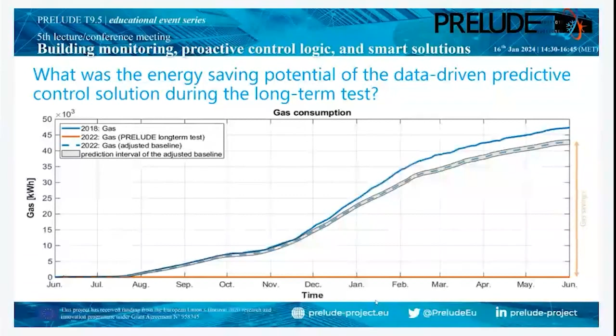Because of the reduction of heat loads in our building, we also switched off the gas boiler at the beginning of our long-term test. In the past, we used the gas boiler for heating purposes. Because of the reduction of the heat losses, we tried to use the heat pump also for heating. Because we only use the heat pump for heating and cooling, we only need electrical energy, we don't need any gas. Therefore, we have 100% gas savings compared to the adjusted baseline. These are more than 4,000 cubic meters, or more than 40,000 kilowatt hours.